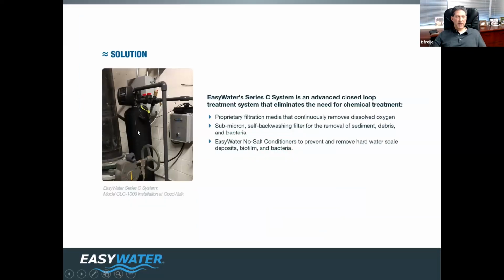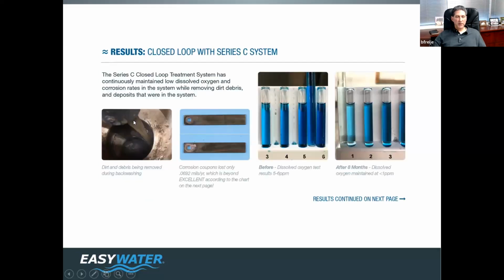On the closed loop side, a backwashing style Series C. Look what's going down the drain with the backwash water. That's metal that we're literally removing, high iron content deposits from all the coaxial heat exchangers, etc. Dissolved oxygen before, you can see by the shade of blue between 5 and 6. After, the glass ampule's clear, meaning there's little to no dissolved oxygen.